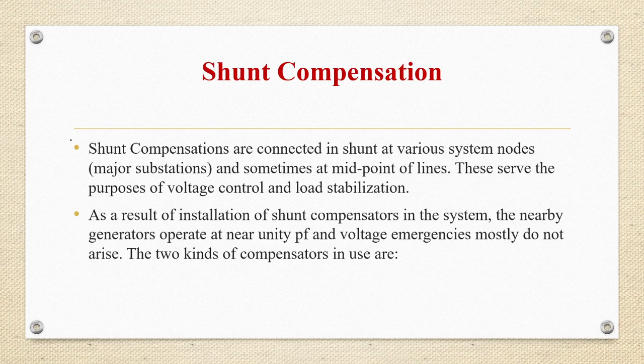So what are the shunt compensators serving? They are serving the purpose of voltage control and load stabilization. As a result of installation of shunt compensators in the system, nearby generators will operate at near unity power factor and voltage emergencies mostly do not arise.